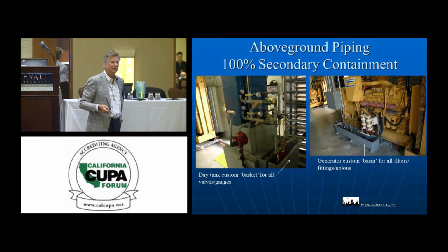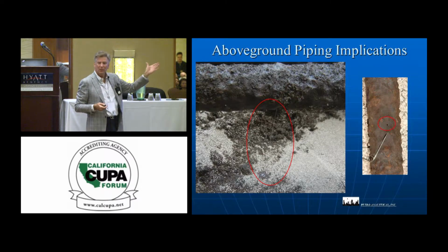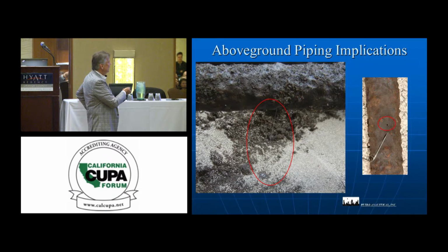You know, I was really hoping in the back you could see this. I took this photo myself because I couldn't believe it. We installed a brand new system. It was all up and running, and we were demoing the old system. And we wanted to test the line just to see where we were before we demoed it. And there is a tiny pinhole right there, and you can see it was just starting.